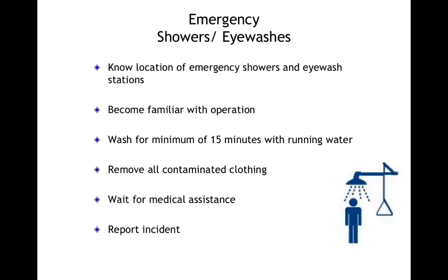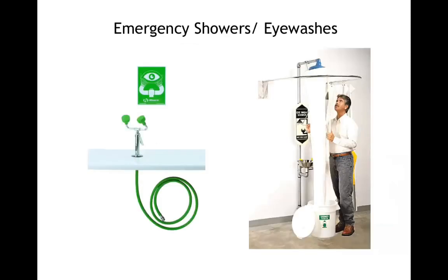Emergency shower, eye wash, everybody should know what are the areas where you have these eye washes or emergency showers, and people should know how to use them. And wash for a minimum of 15 minutes with running water. Remove all contaminated clothing. Wait for medical assistance. Report incidents. And keep a record of all actions taken.